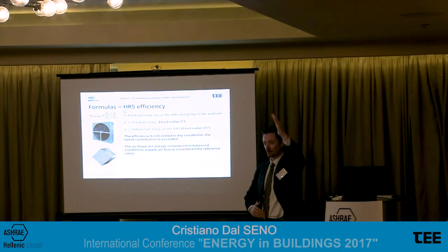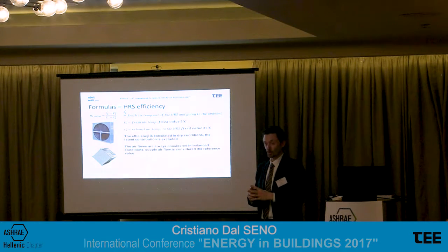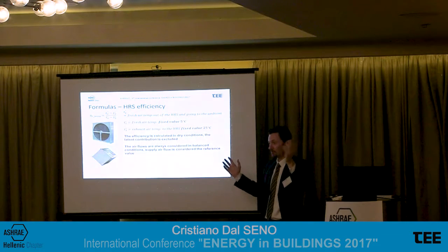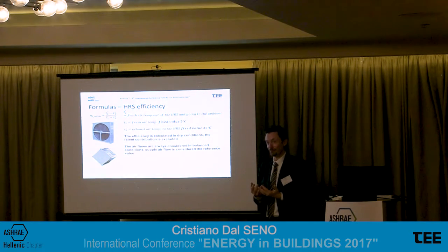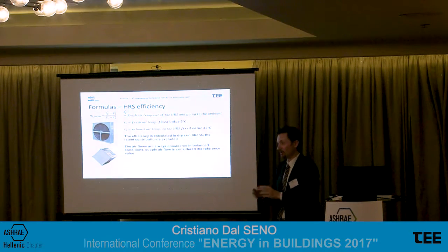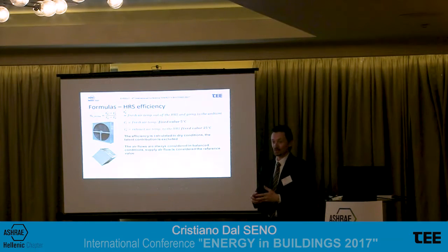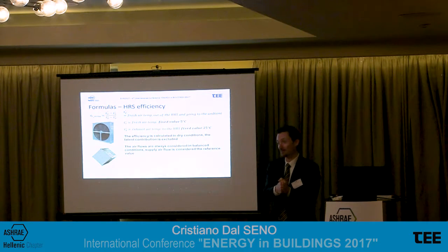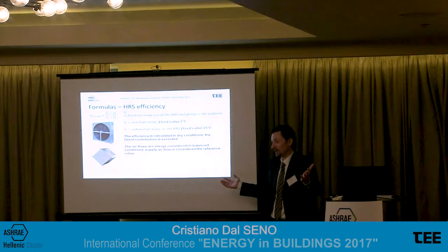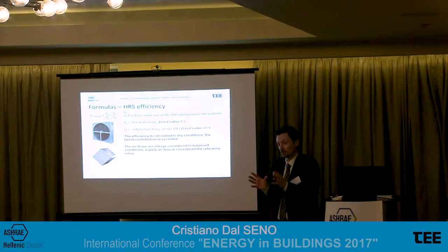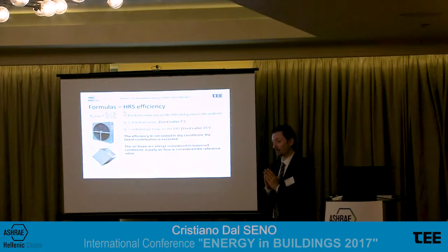Unbalancing in this way the parameters of the calculation will create small plate heat exchangers with incredible efficiencies, because you are working in very positive conditions. So if you play with the parameters and change them in order to obtain the efficiency you want, you can do whatever you want without modifying the structure of the unit. The norm is saying something different.